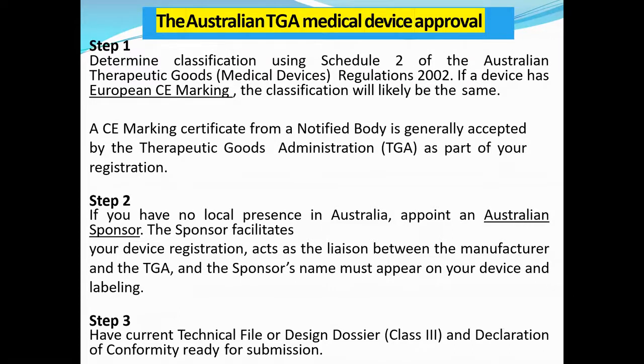That is why people are behind getting the CE mark. Once they develop or design a product and start manufacturing, everybody is behind quality management certification, that is 13485, and getting the CE mark. So the classification will likely be the same. If you have the European CE mark, you can easily enter TGA. A CE marking certificate from a notified body is generally accepted by the TGA as part of your registration.